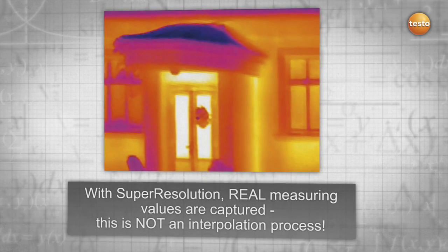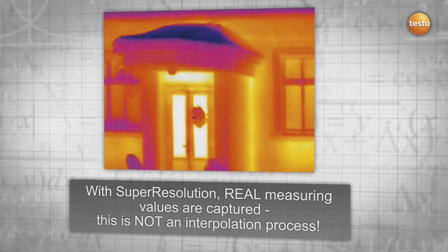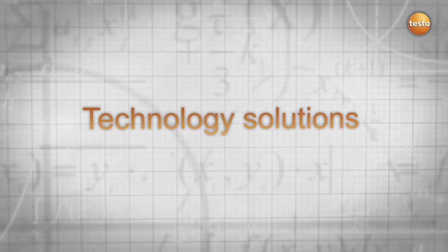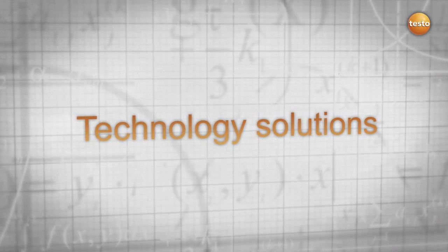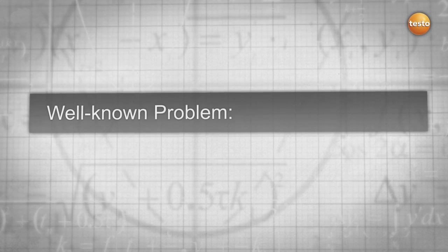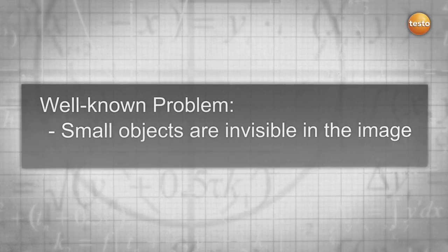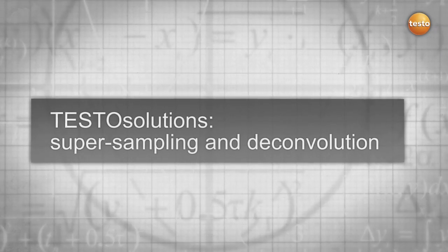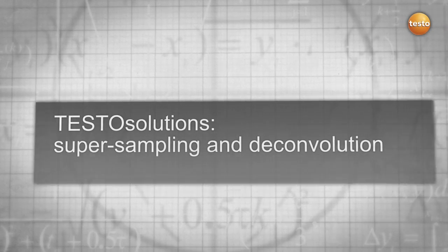The problem is well known: small objects are invisible in the image, and even if visible, the measured values are not correct. The Testo solution: super sampling and deconvolution. By using multiple images, super sampling, and complex mathematics deconvolution, you get more information out of your thermal images.